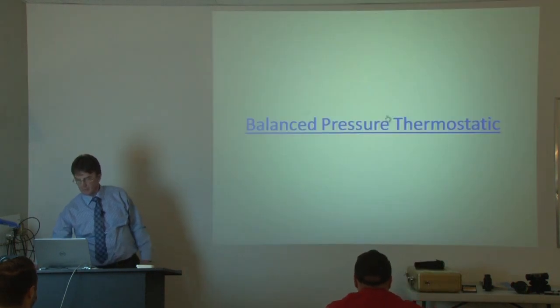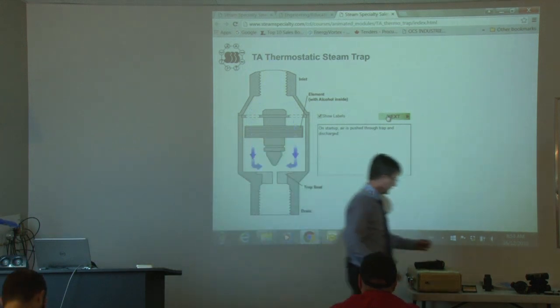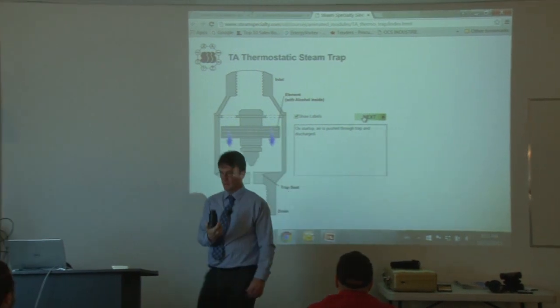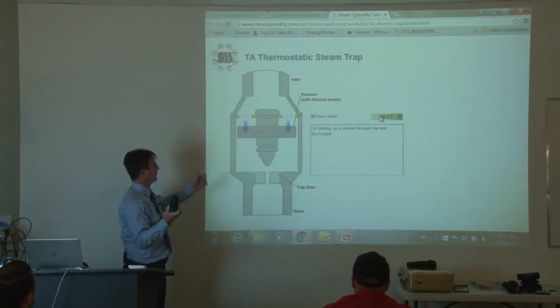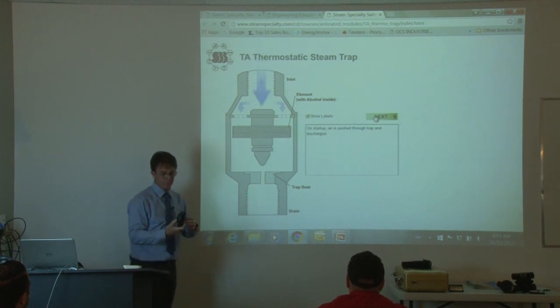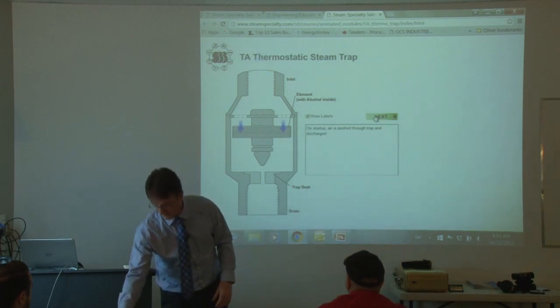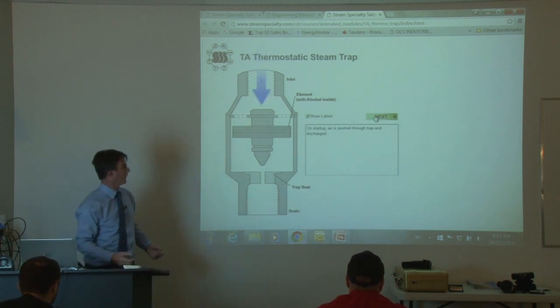Balanced pressure thermostatic — this shows a different style, a vertical style. This is actually an air vent, a thermostatic air vent. The principle is the same whether it's an air vent or whether the company calls it a steam trap. Exactly the same principle. It's normally open, and as the heat goes up inside the body, the element expands and closes it off.